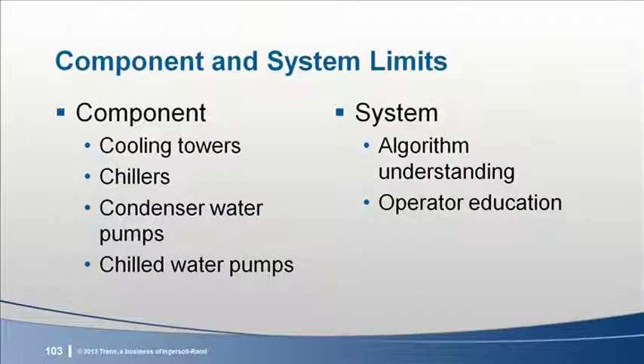Mick, we've mentioned the importance of understanding each component's operating limitations. Would you please dig a little deeper into that? Surely. Now that we've discussed system optimization, we need to step back and understand the boundary limits. That is, when do we need to deviate from theoretical optimum control so that the components and system continue to operate properly? From a component standpoint, we'll examine the cooling tower, chiller, and pump boundaries. Then we'll discuss a couple system limits.